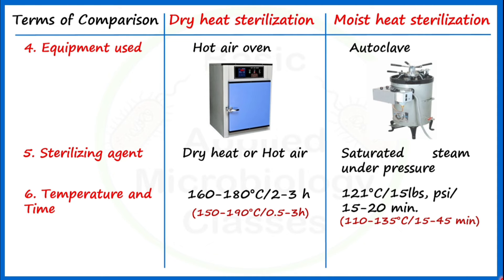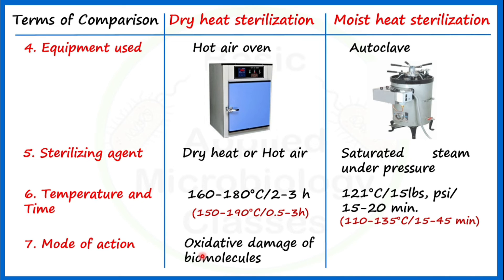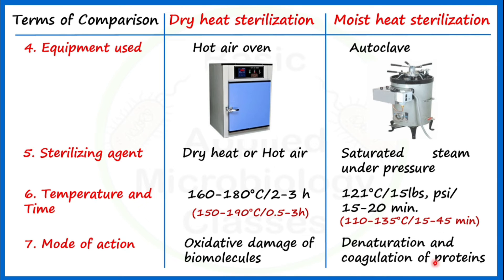The seventh point of difference is the mode of action — how each method results in killing of microorganisms. Dry heat, used in a hot air oven, causes oxidative damage of biomolecules, which results in killing of living entities. The autoclave results in denaturation and coagulation of proteins of microorganisms or any living entities, which leads to sterilization by moist heat.